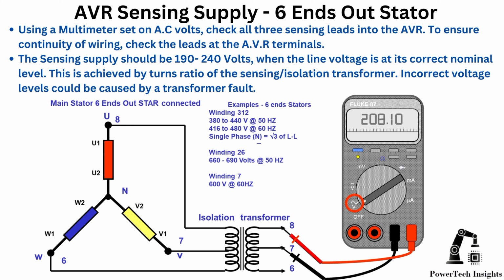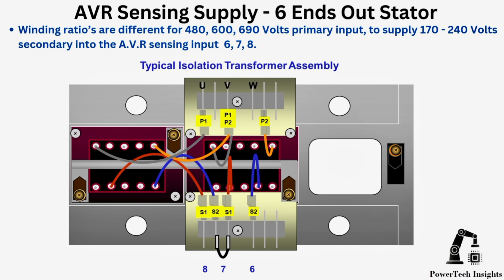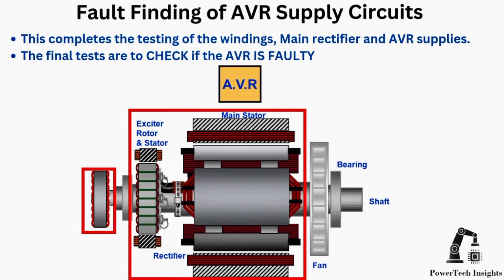This is achieved by the turns ratio of the sensing isolation transformer. Incorrect voltage levels could be caused by a transformer fault. Winding ratios are different for 480, 600, 690 volts primary input to supply 170 to 240 volts secondary into the AVR sensing input 6, 7, 8. This completes the testing of the windings, main rectifier, and AVR supplies.